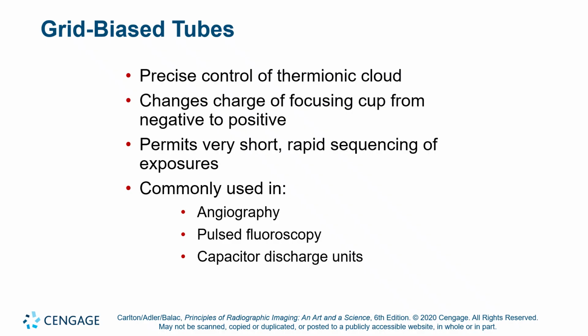Okay. So what that does is it makes it so we can take pulsed fluoroscopy. Okay. It also works pretty handily with capacitor discharge units, but the real benefit is in dose reductions in fluoro. Because you can sync up the pulses of the X-ray tube with, let's say you have software that can process 30 frames a second. And so you send bursts of X-ray at 30 hertz, 30 cycles per second, and that matches up with how fast your detector can process images.